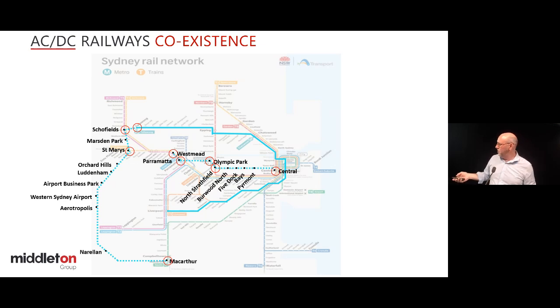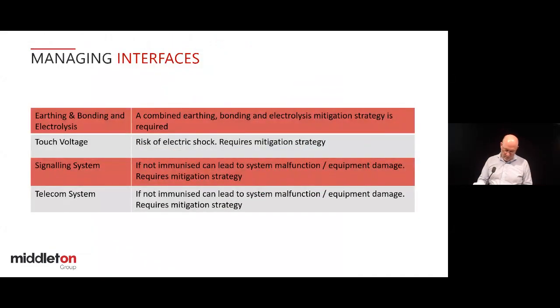So let's have a look at the issues. So here's a bit of a list, and I'll summarise with a key takeaway here. Traditionally, 25 kV systems and 1500 volt systems use slightly different earthing arrangements. For example, 25 kV, as Stephen pointed out, has a connection to ground. DC rail systems traditionally don't, because that doesn't help you with stray current electrolysis. It tends to contribute to it. You want to isolate your tracks, your rails, from the ground. Two effectively slightly competing earthing systems.